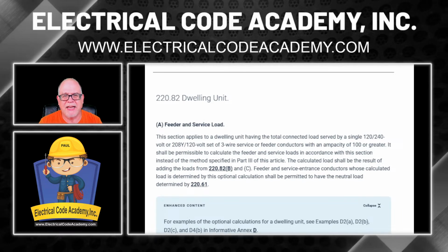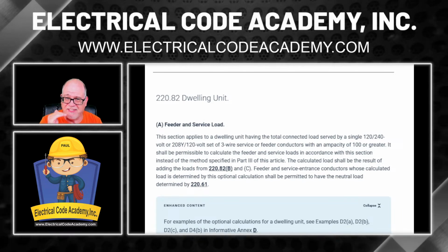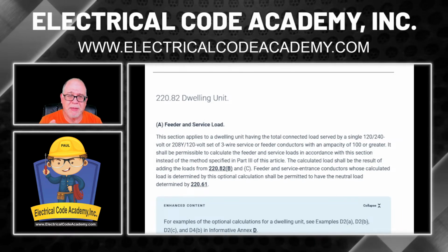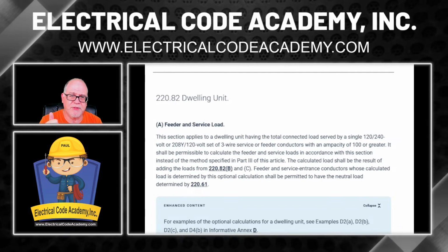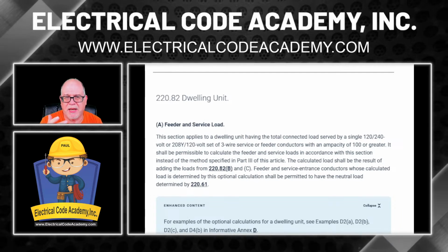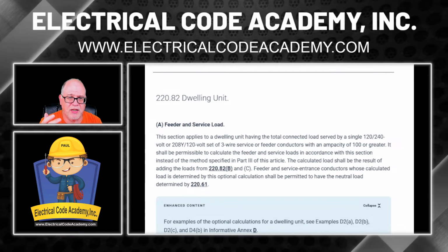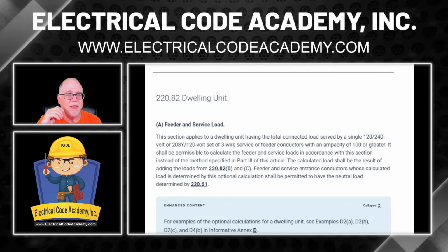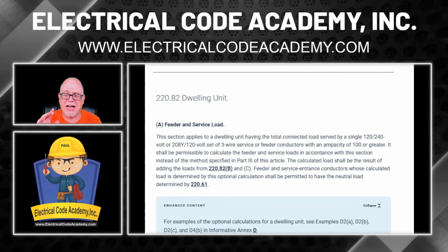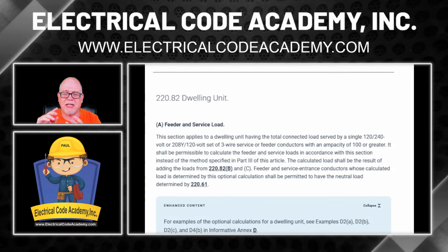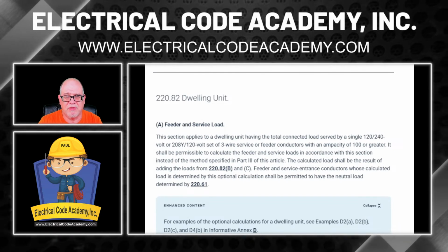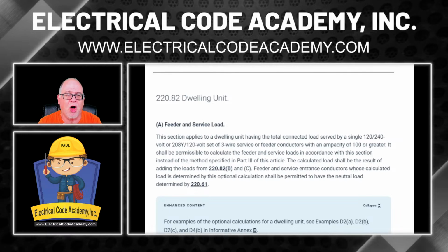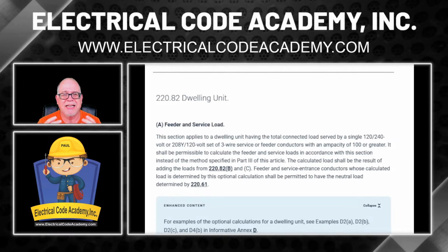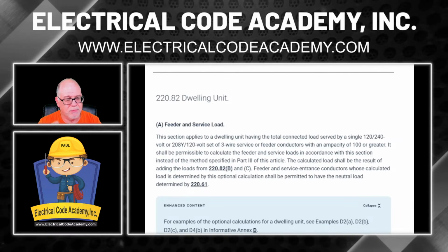This is broken down into an A, a B, and a C. B is the one that deals with the 3 VA per square foot, and talks about adding up all the nameplates, the first 10,000 at 100% and the remainder at 40%. We're not doing any of that, because we're not looking at cooking, we're not looking at appliances, and we're not looking at 3 VA per square foot. All we're being asked to do is deal with the heating and air conditioning.